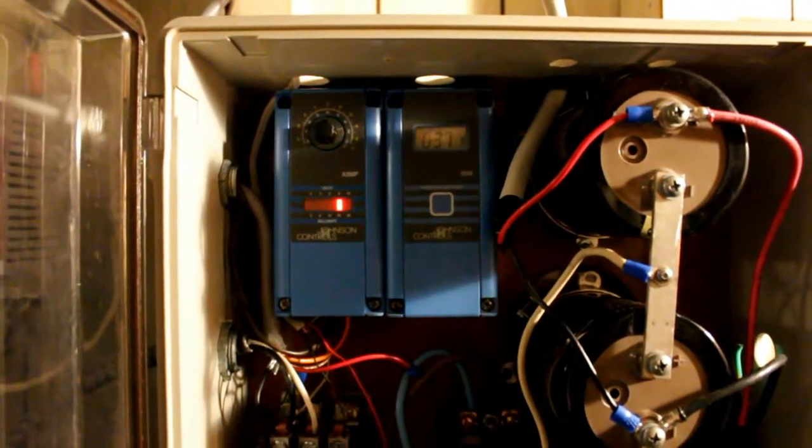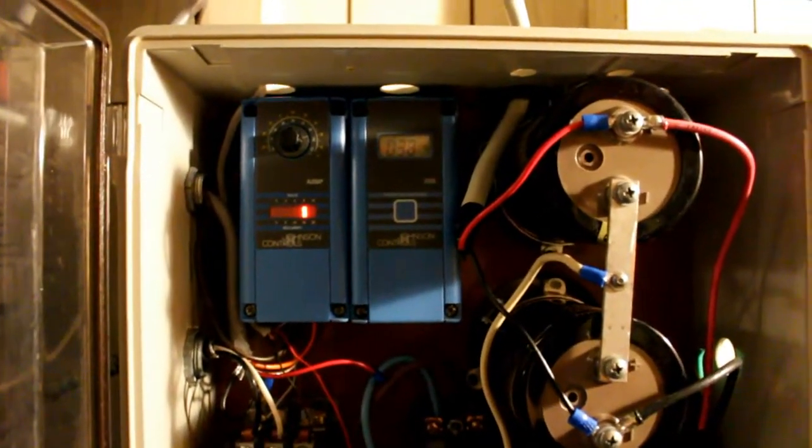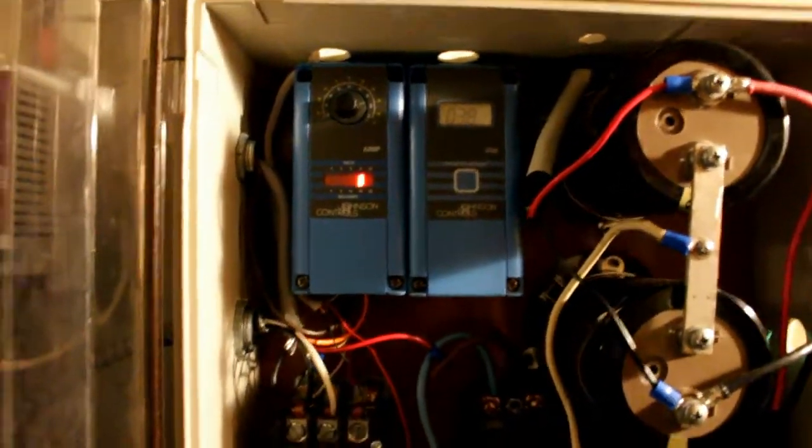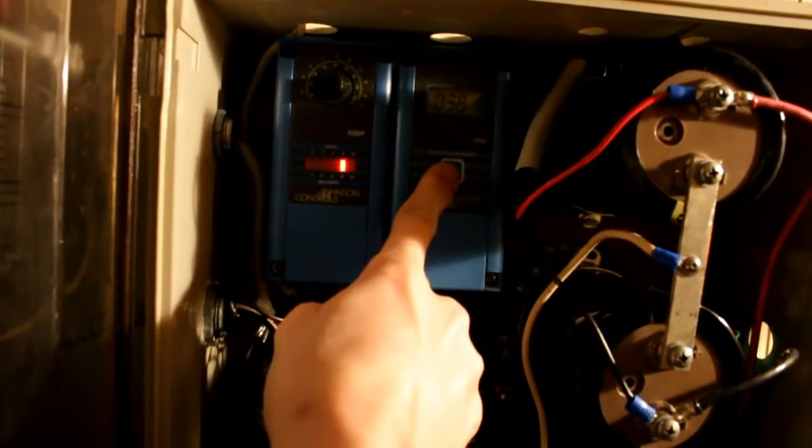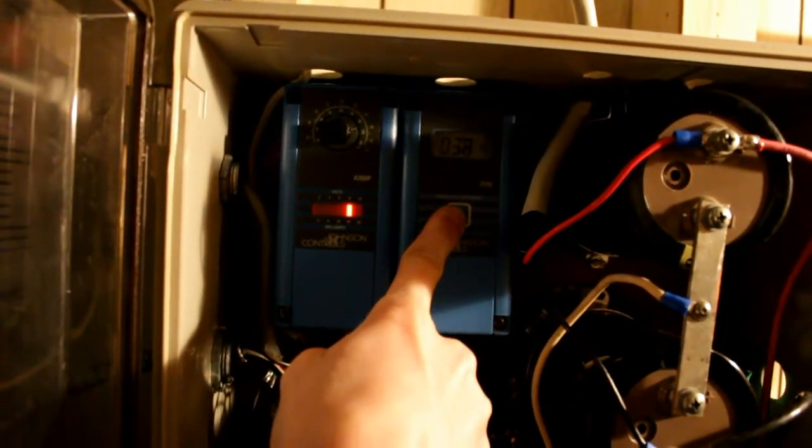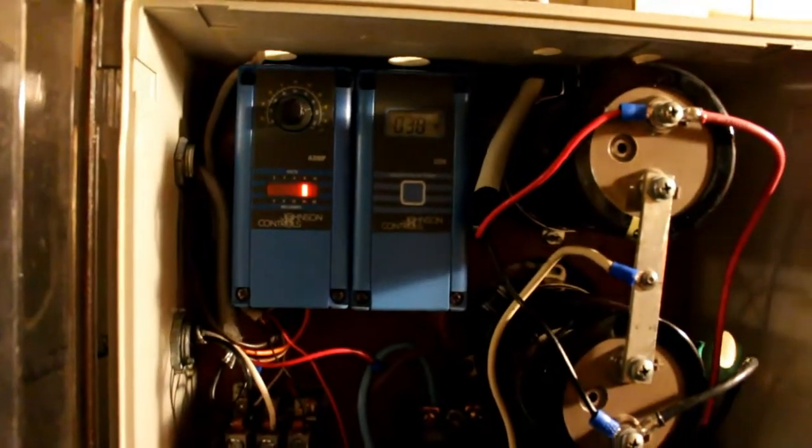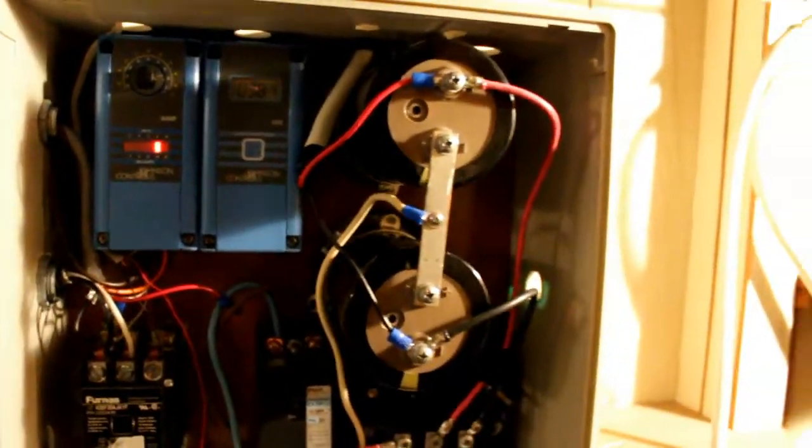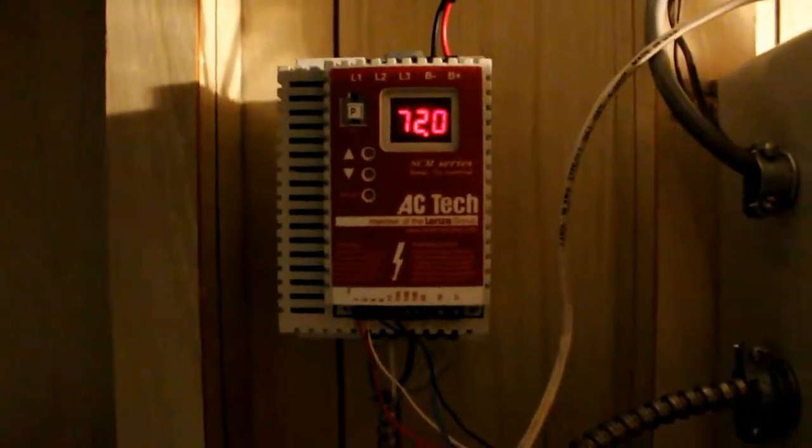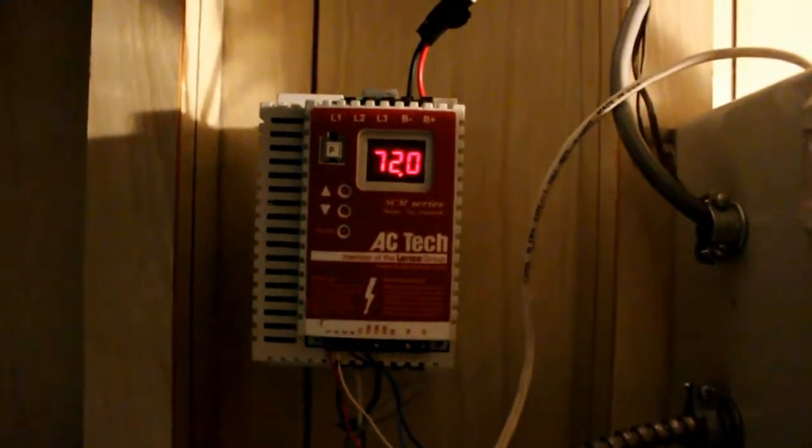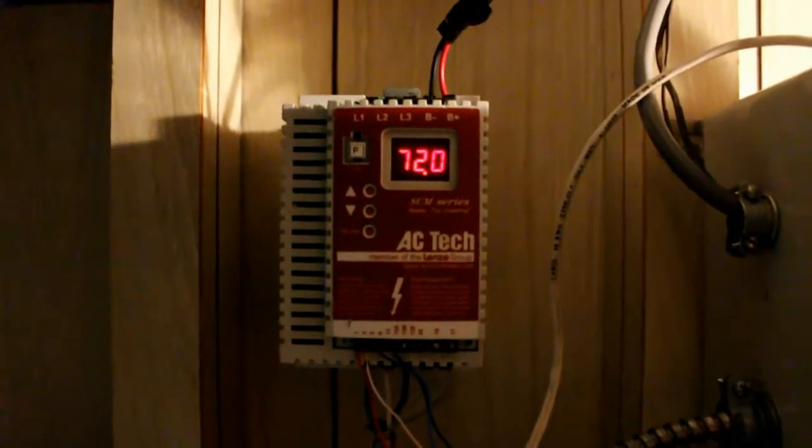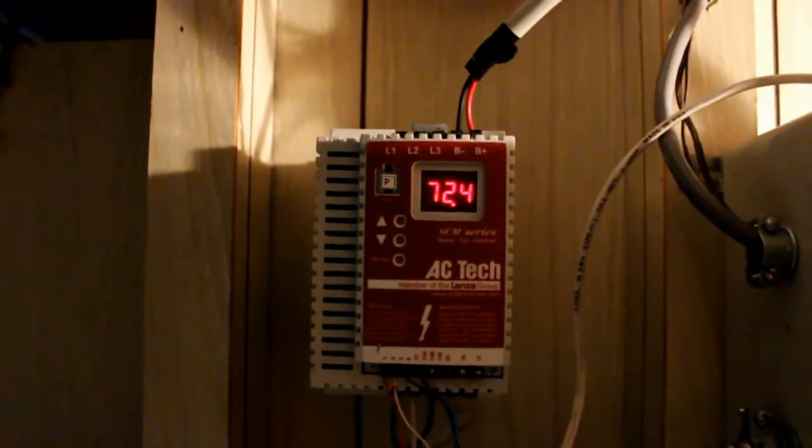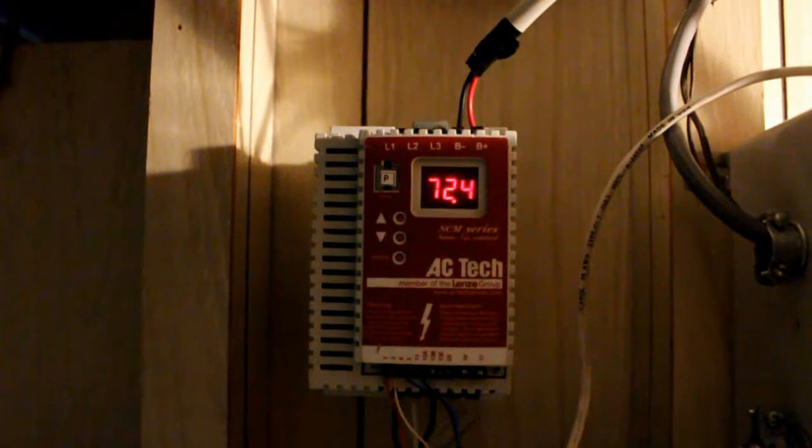Now this is in heating mode. It's about 62 degrees outside, and it's programmed to maintain the line temperature at 38 Celsius. It's much more stabilized now. As you can see, the frequency doesn't vary nearly as much - it usually stays right on. Maximum frequency allowed is 80 Hertz and minimum is 25, so it stays pretty stable now.